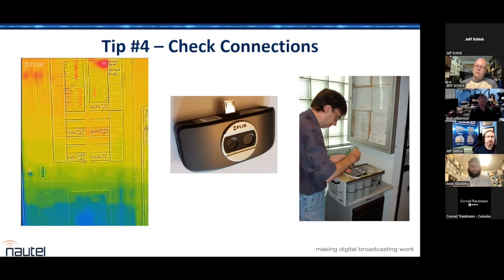Copper is malleable. It will compress to displace air within the connector. So unless you're putting a lug on with a proper hydraulic crimp tool that displaces all of the air, that copper will deform to displace that air, and that connection just became a little looser.